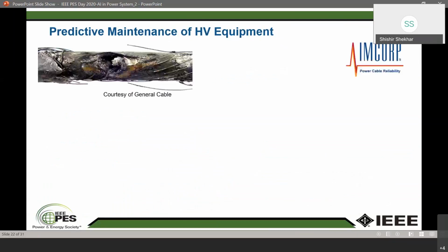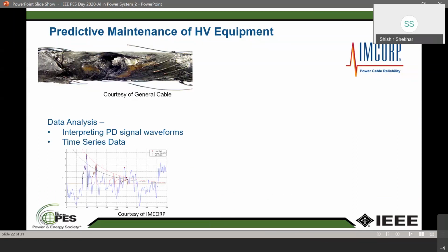So one of the important applications in the asset management area is predictive maintenance of high voltage equipment. High voltage equipment can be your disconnect switches, your circuit breakers, your transformers, your overhead lines, your underground cables. Some of the equipment is much easier to manage, and some is a lot more challenging to manage. I think the two most challenging to manage are your transformers and your underground cables. A transformer is a very complex piece of equipment. While it has been used for many years, understanding when a transformer might fail is still a big challenge in the industry.